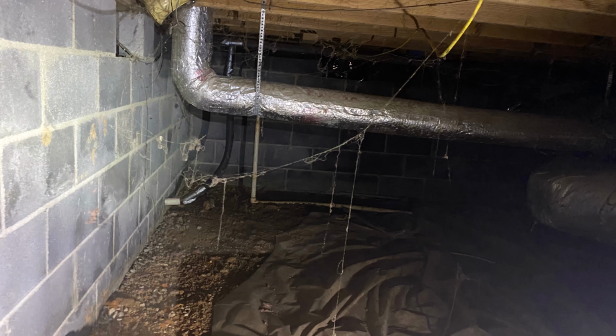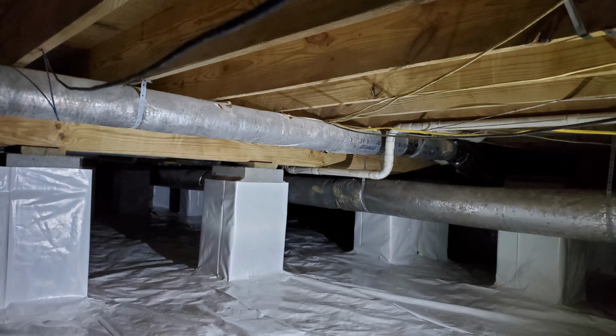The second is conduction. Even if that duct were perfectly airtight, if it's carrying warm air through a cold crawl space in January, heat is still trying to move through the duct wall toward the colder crawl space. Same thing in reverse during the summer. That's why ducts outside the conditioned space need to be both sealed and properly insulated. Sealing handles the air leakage, insulation slows down the conductive heat transfer. So even when you've got ductwork running through an unconditioned crawl space, you're not just dealing with one problem. You can be leaking conditioned air out of the system and losing heat through the duct itself all at the same time. That means your HVAC system has to work harder just to deliver the temperature you already paid for.